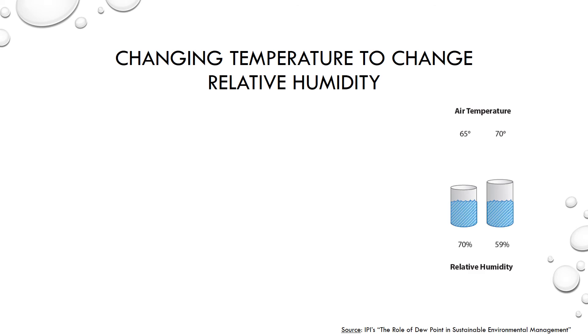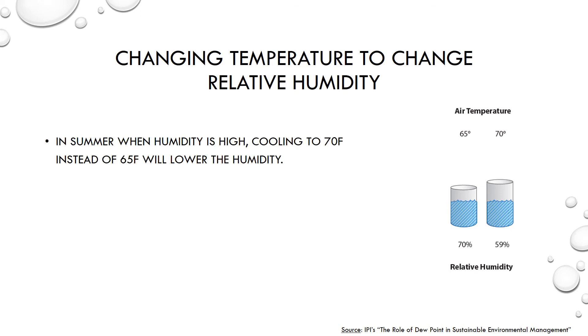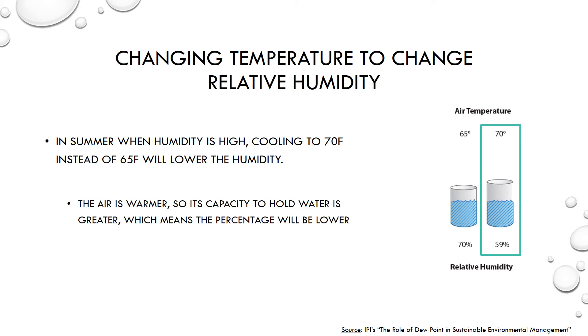When you cannot control the amount of moisture in your space, you can change the temperature to change the relative humidity. Missouri summers are hot and the humidity is high. Without removing any moisture from the air, cooling to 65 degrees with this volume of water present would cause the relative humidity to be quite high, as we can see in the diagram. Cooling to 70 degrees instead would lower the humidity because the warmer air has a greater capacity to hold water, so that same amount of moisture takes up less space at 70 degrees than it does at 65 degrees.